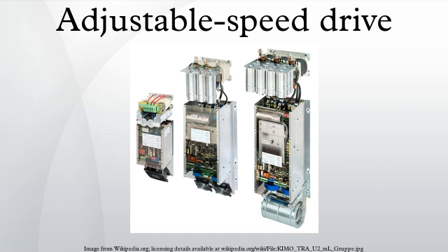AC drives. AC drives are AC motor speed control systems. A slip-controlled wound rotor induction motor drive controls speed by varying motor slip via rotor slip rings, either by electronically recovering slip power fed back to the stator bus or by varying the resistance of external resistors in the rotor circuit. Along with eddy current drives, resistance-based WRIM drives have lost popularity because they are less efficient than AC-DC-AC-based WRIM drives and are used only in special situations.